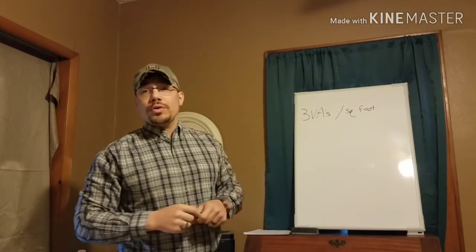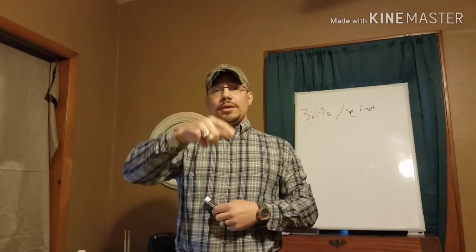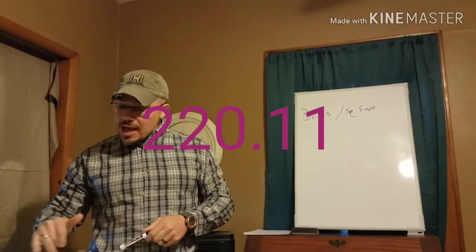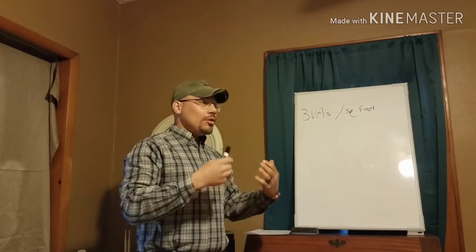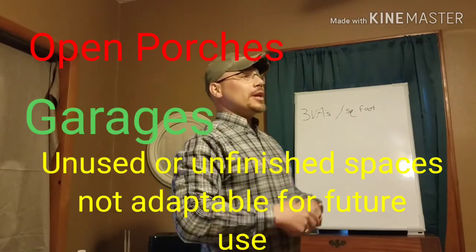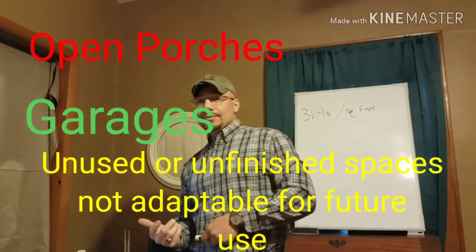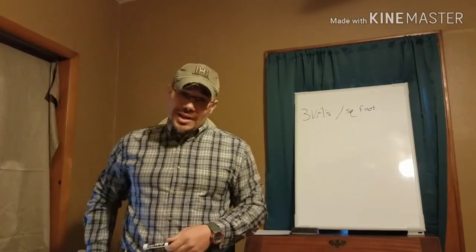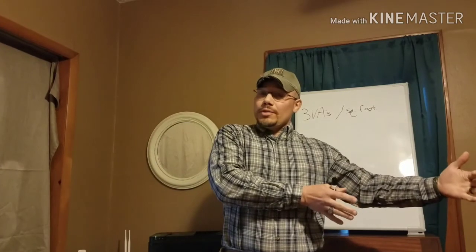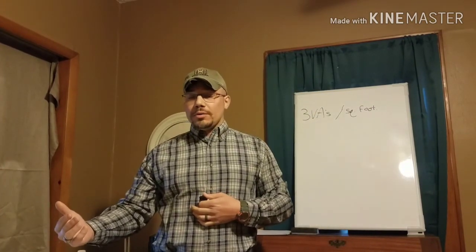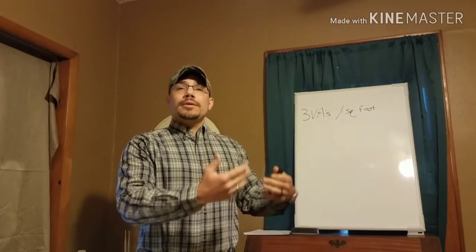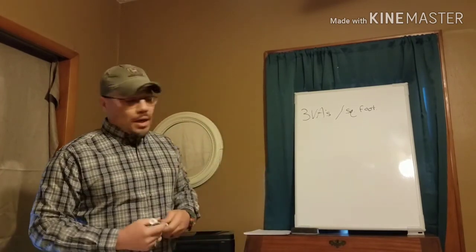3 VAs per square foot. That square footage is the complete outside dimensions of the house with some exceptions. If we look at Article 220.11, it says that the things that are not included are open porches, garages, and unused or unfinished spaces that cannot be put into habitable rooms later. The reason we have to think that way is because we don't want them to adapt it later if it's possible to adapt, and then our service calculation would have been wrong. If it's something that can't be adapted later, a portion of the house that cannot be adapted for a livable space later, then we don't have to count that.